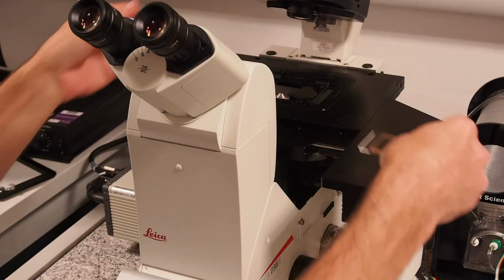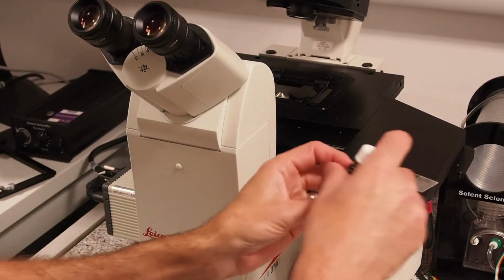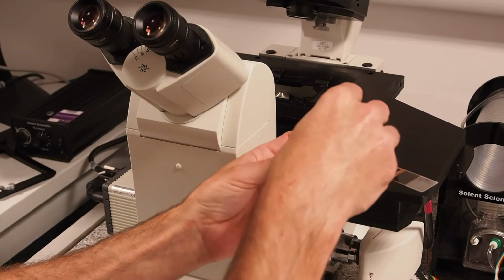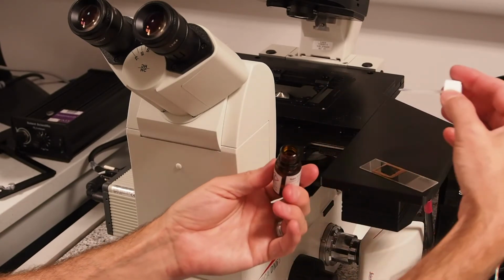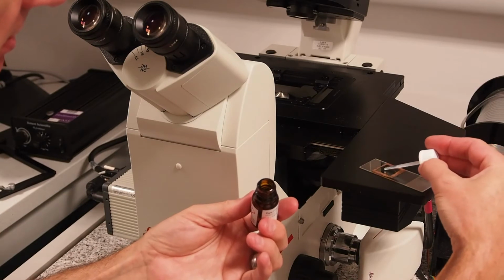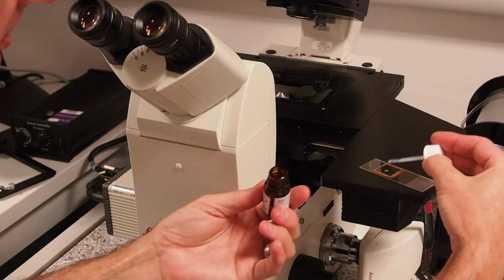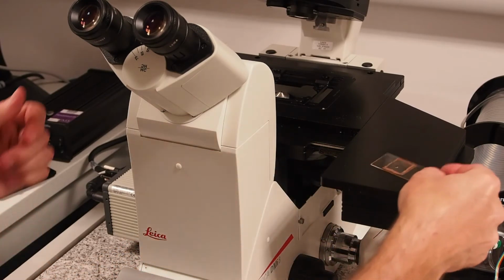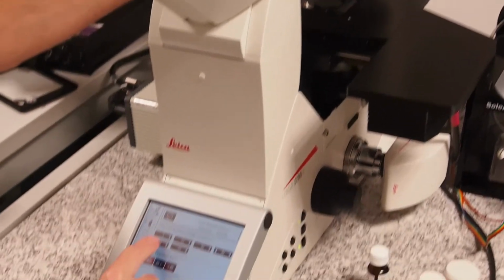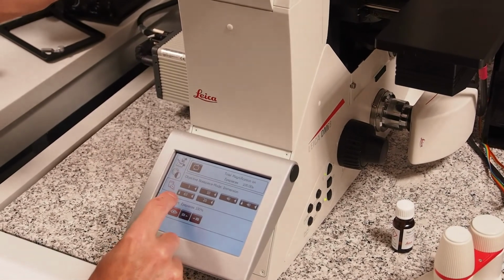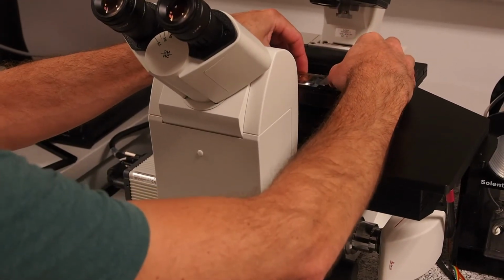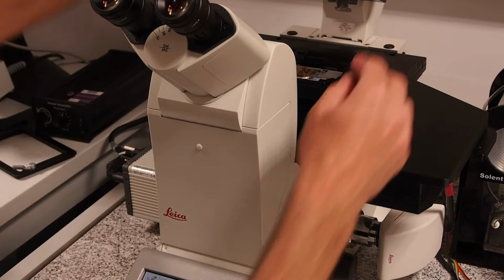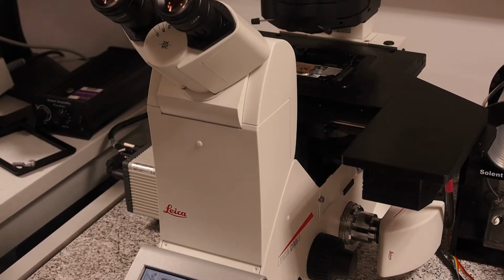You can now push back the condenser arm, remove your sample, and place a small amount of oil on your sample in the region you are visualizing. Press the lens button again to rotate the lens into position. This is so you do not accidentally drop oil onto the air objective. Reapply your sample to the stage and return the condenser arm to its upright position.